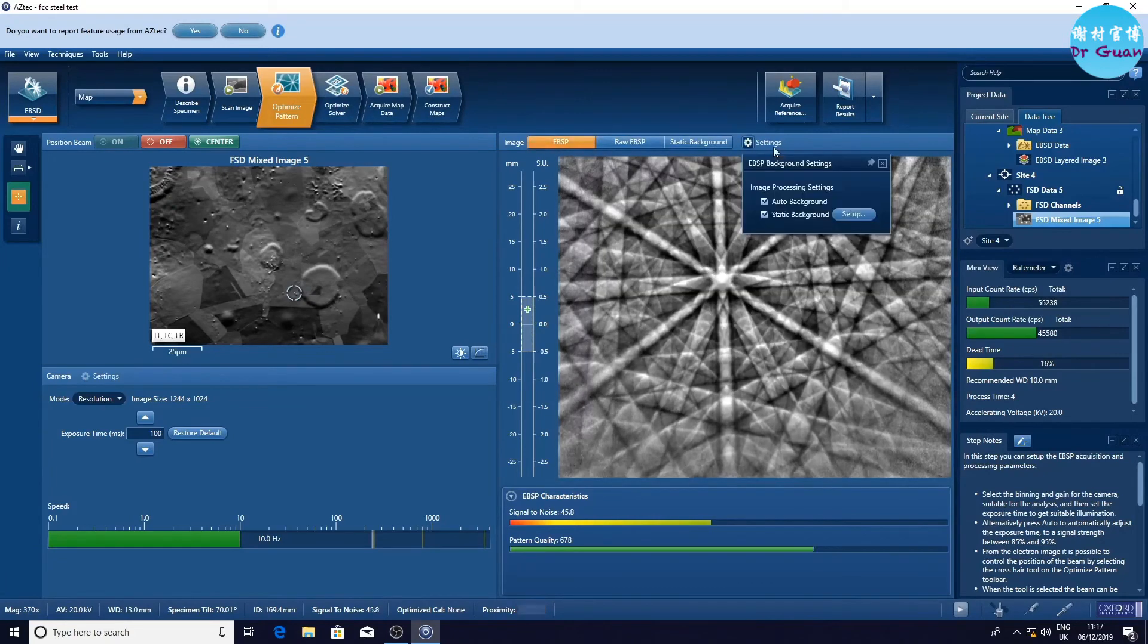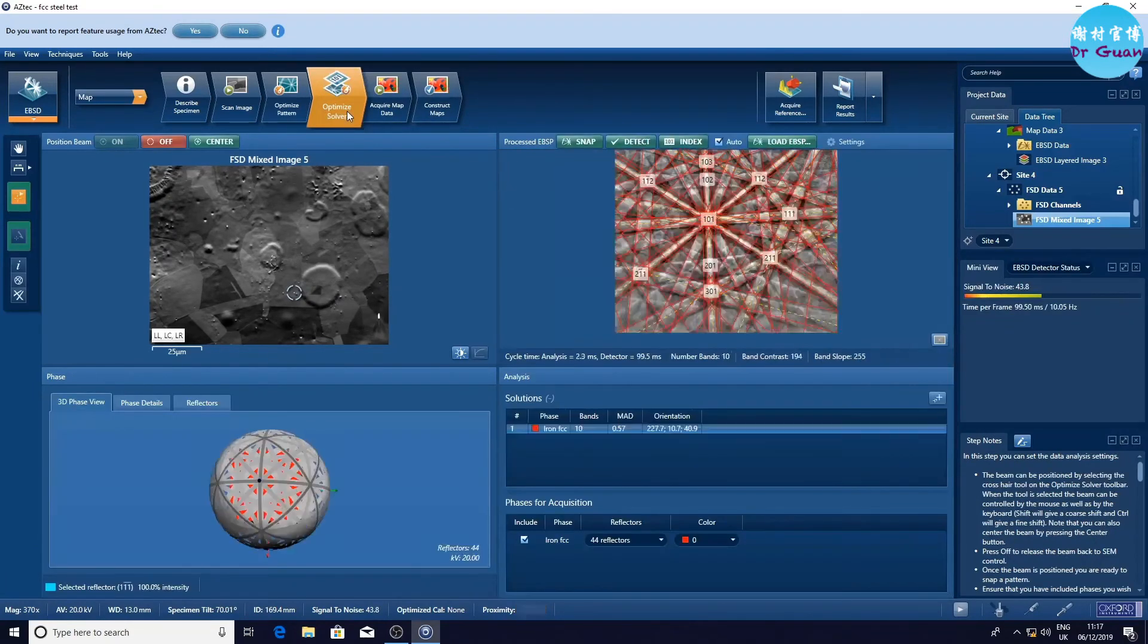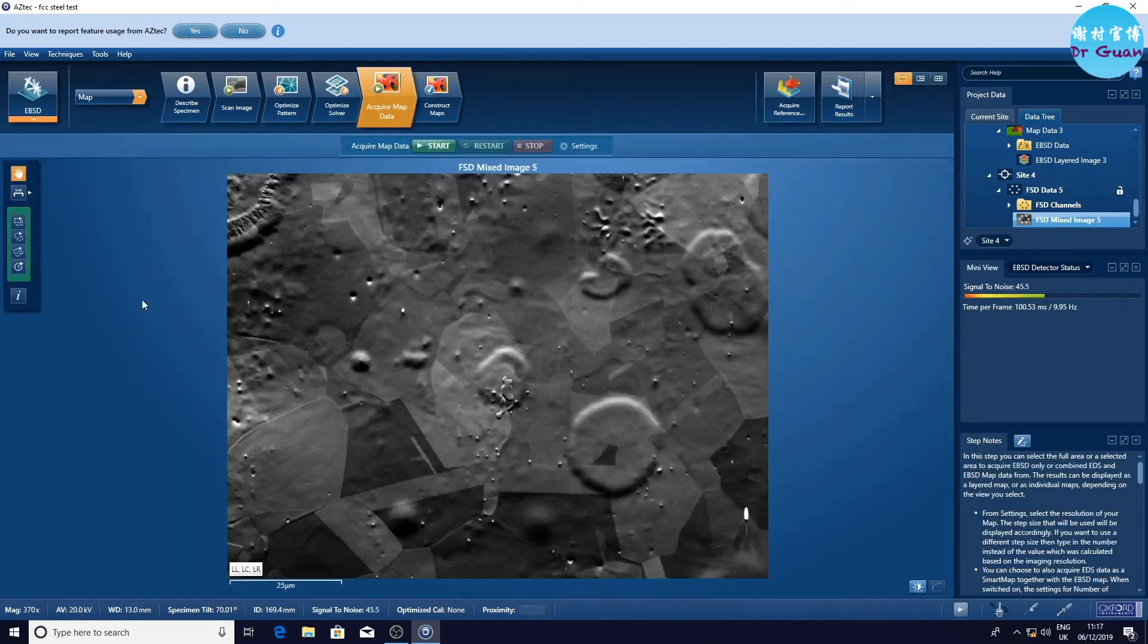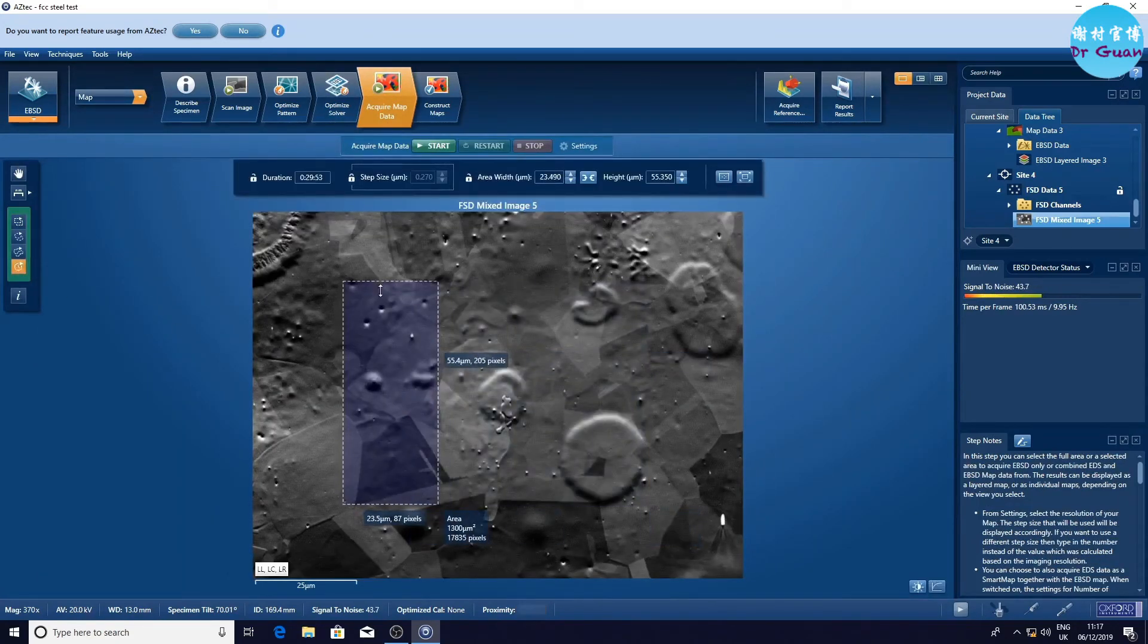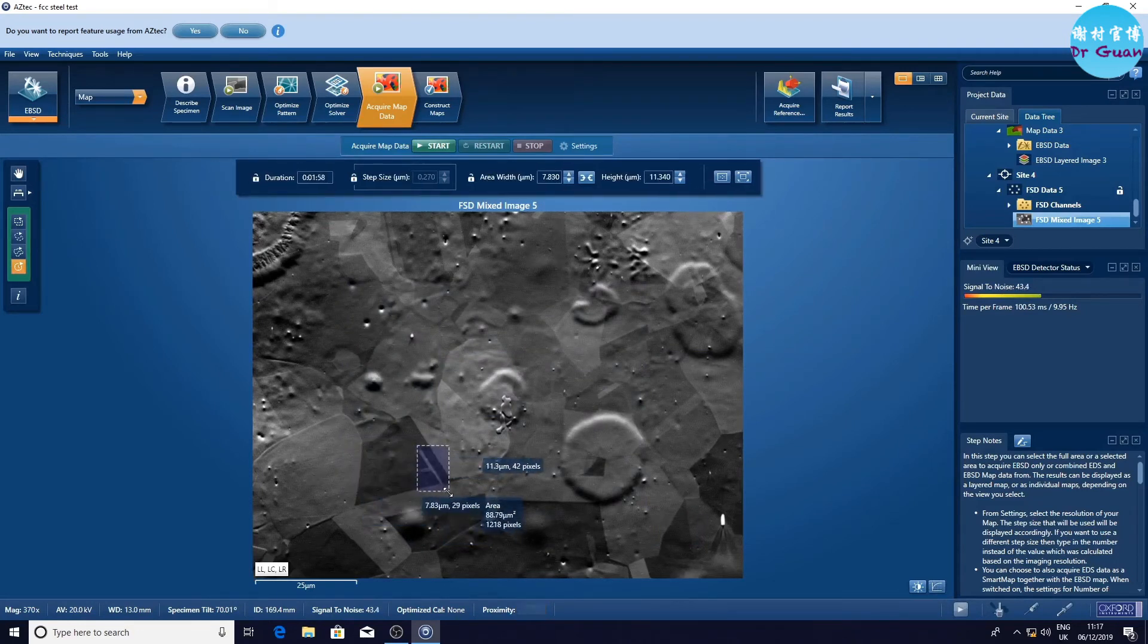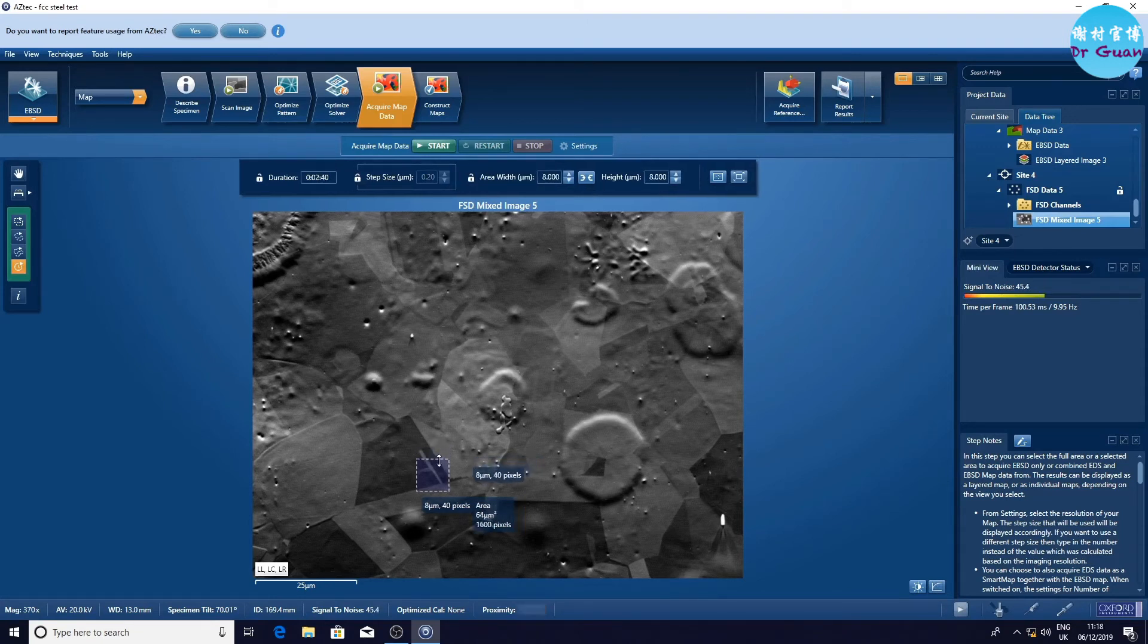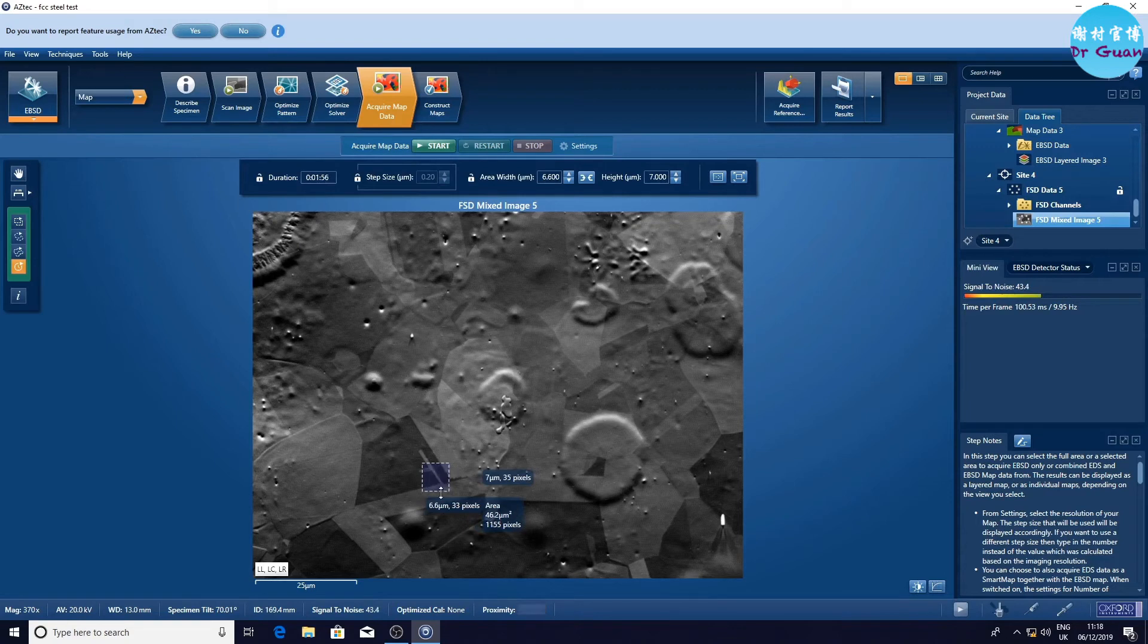We just checked the raw EBSD and static background. Now we are going to do the optimized solver. Now you can see the image is quite good. The MAD is only 0.3. Now we are going to collect some high resolution Kikuchi patterns. Because it's only for the demonstration, we only look at the small area. I'll choose the step size 0.2 microns. I'm trying to reduce the area to decrease the time.